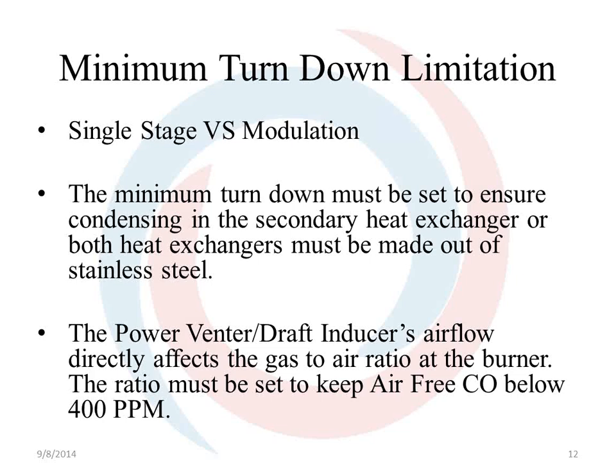The other problem is the air-to-gas ratio, which is usually maintained at 1:1. However, as you turn down the gas in a typical system, the air remains constant. This can lead to an increase in carbon monoxide production above the legal 400 parts per million limit. In order to eliminate this, the minimum turn down must be either set above the point where this occurs, or use a 2-speed or variable speed power venter to get past the 1:1 ratio. Combined, these determine the minimum fire rate for the unit. So, problems with larger capacity units at 90% are very, very real.